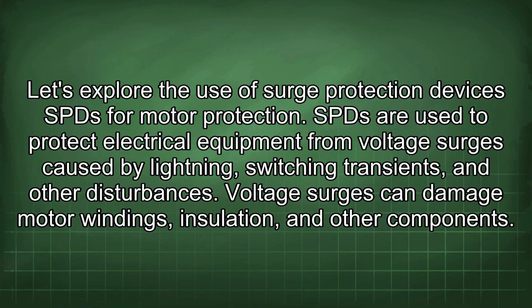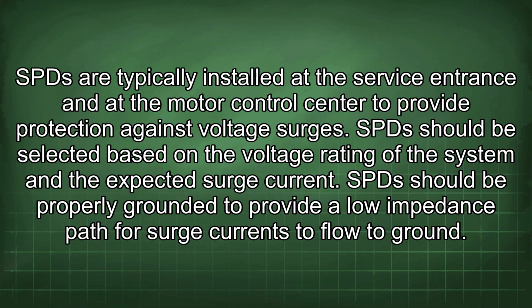SPDs are used to protect electrical equipment from voltage surges caused by lightning, switching transients, and other disturbances. Voltage surges can damage motor windings, insulation, and other components. SPDs are typically installed at the service entrance and at the motor control center to provide protection against voltage surges. SPDs should be selected based on the voltage rating of the system and the expected surge current. SPDs should be properly grounded to provide a low impedance path for surge currents to flow to ground.